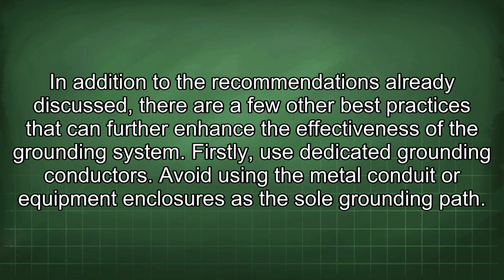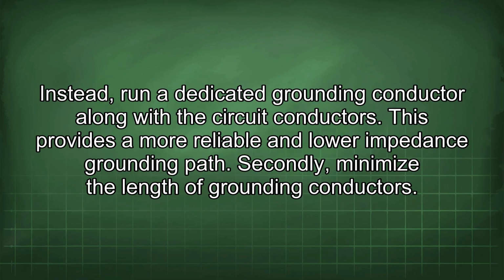In addition to the recommendations already discussed, there are a few other best practices that can further enhance the effectiveness of the grounding system. Firstly, use dedicated grounding conductors. Avoid using the metal conduit or equipment enclosures as the sole grounding path. Instead, run a dedicated grounding conductor along with the circuit conductors. This provides a more reliable and lower impedance grounding path.